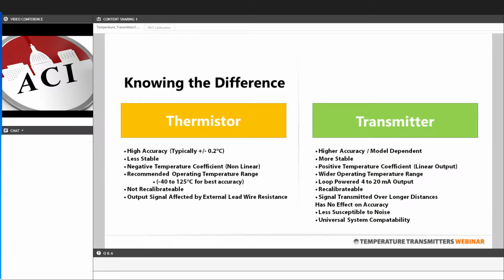When using a 4 to 20 current signal, you can transmit that signal over much longer distances than you can send a resistive signal. As the lead lengths or the transmission length increases with a resistive signal, the resistance increases, so that can affect the output. These current signals are also less susceptible to noise, whether that be other electrical noise from other electrical signals or from RF, wireless, or any other types of signals.